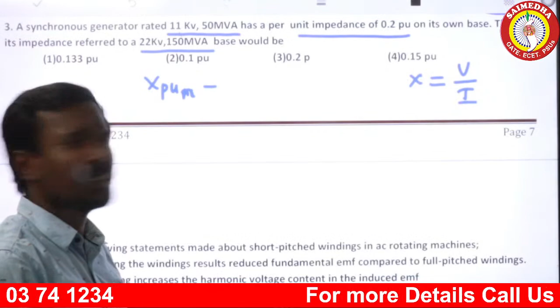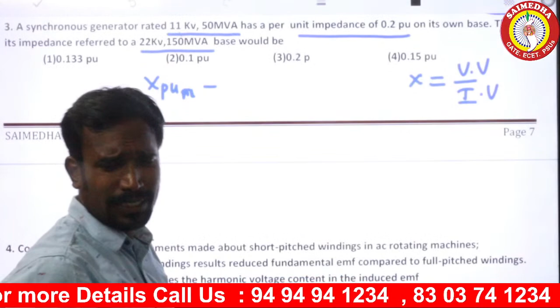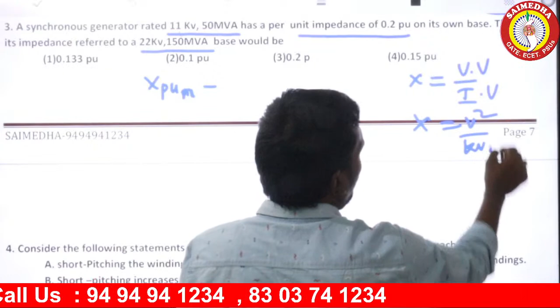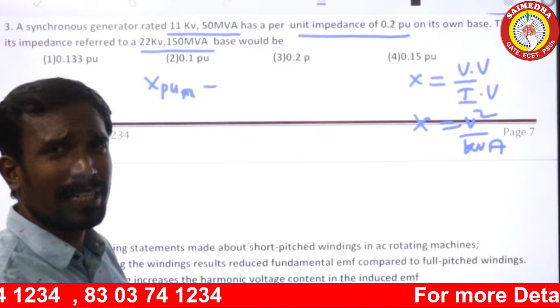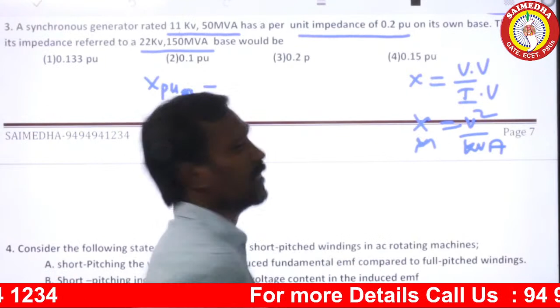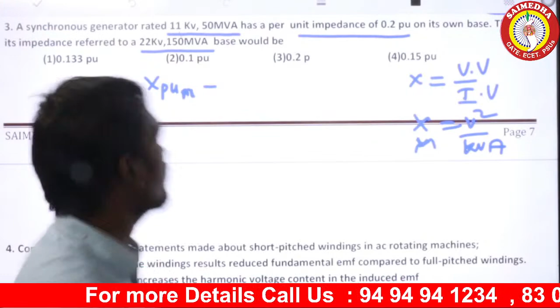X reactance, okasari choodandi. Generally, reactance is nothing but voltage by current, that is called impedance, that is called reactance. If you multiply numerator and denominator by voltage again, then x is equals to V square by kVA. That is the per unit reactance, per unit impedance or per unit reactance.